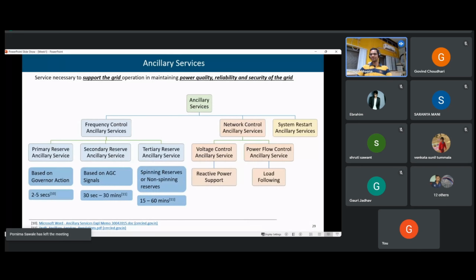Primary reserve is required for a very short duration, for sudden changes in frequency - we use this to adjust the frequency to the nominal frequency. When primary reserve is not enough, we go for secondary reserve, then tertiary reserve. The duration increases: primary reserve acts within 2 to 5 seconds, based on governor action. Secondary reserve reacts within 30 seconds, and if a generator is providing that service, it will have to ramp up to its capacity within 15 minutes and then maintain it till 30 minutes or half an hour.